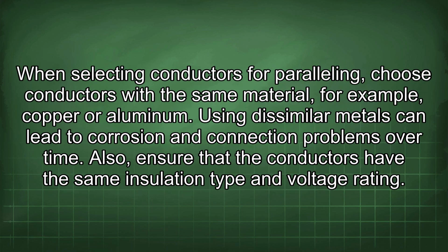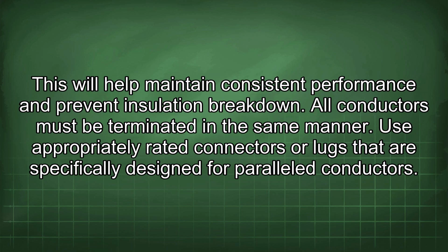When selecting conductors for paralleling, choose conductors with the same material, for example, copper or aluminum. Using dissimilar metals can lead to corrosion and connection problems over time. Also, ensure that the conductors have the same insulation type and voltage rating. This will help maintain consistent performance and prevent insulation breakdown.